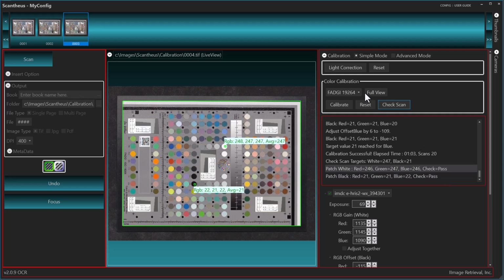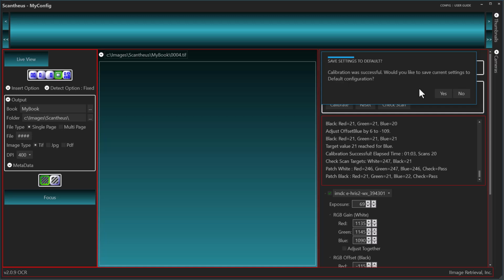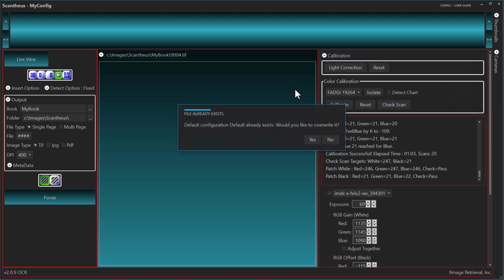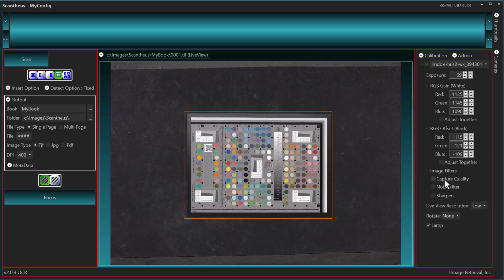When you exit calibration, it prompts to see if you want to save it to a default configuration. Yes, you do, because that saves your camera settings that are calibrated. I already have a default out here, so I want to override it. Then the last thing I want to do is turn the image filters on that I had turned off within calibration. And that's it.